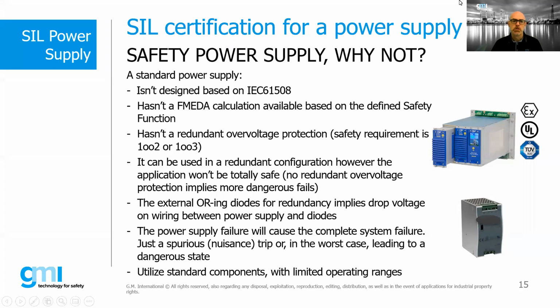And also, standard power supplies use internal components with limited operating range to keep costs down. This affects the lifetime of the device. For this reason, internally to the safety power supply system, components with a higher operating range are used that allow the system to work at a lower stress level. This leads to fewer failures and consequently a considerably longer lifetime than a standard power supply system.